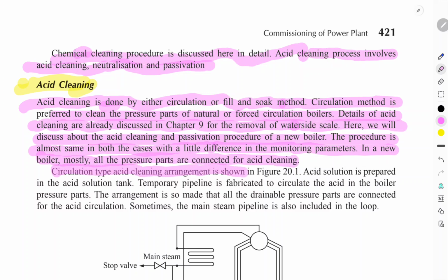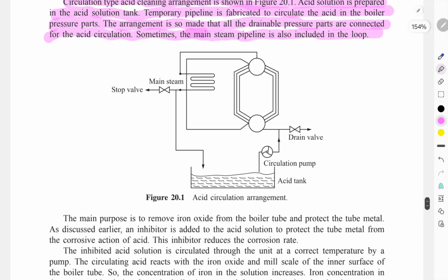The circulation type of acid cleaning arrangement is shown in the figure. Acid solution is prepared in the acid solution tank, and temporary pipelines are fabricated for circulation of the acid through the boiler pressure parts. The arrangement is made for all the drainable pressure parts to be connected for acid circulation, and the main steam line is also included in the loop. So this is the acid tank. The acid is circulated by the circulation pump from here, through the main steam line up to the stop valve, and then comes back to the tank.